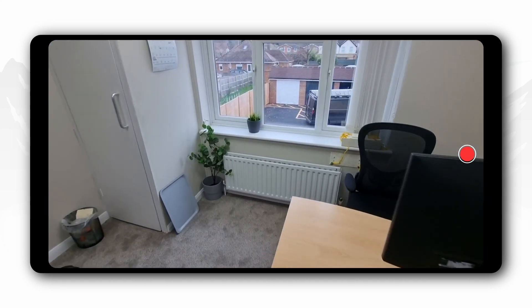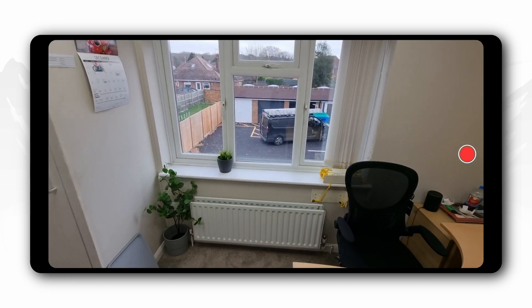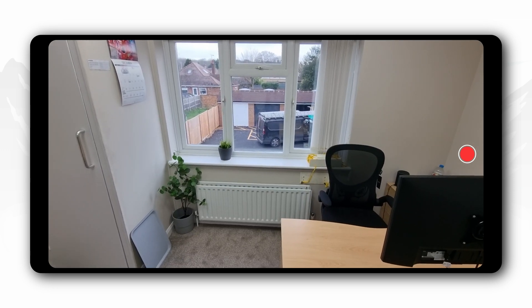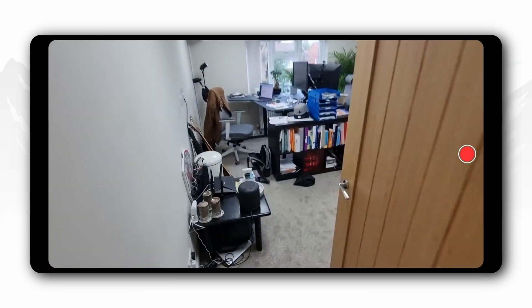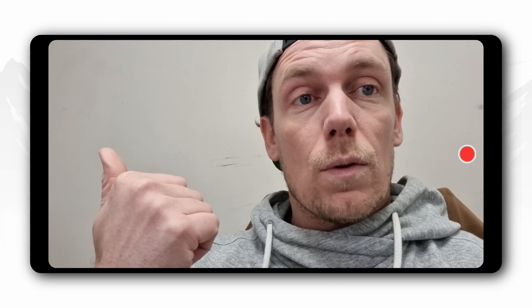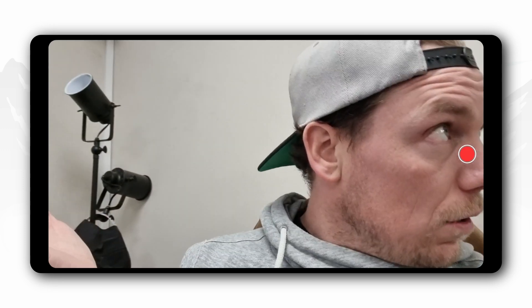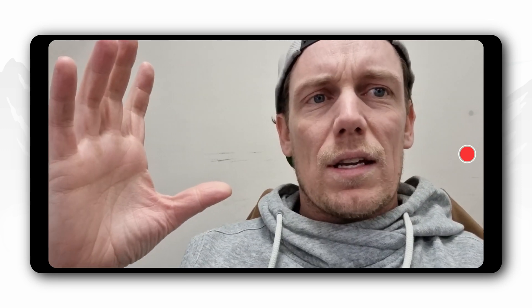And in this room, this room does have a double panel, double convector. However, it's been shortened — not as wide as the window and very short. It's only about 400 or 450mm high, which is abnormal. So an abnormally small radiator in there. My office also has an abnormally small radiator — single panel, single convector. So we've got 200mm of loft insulation, which is very normal. We've got cavity wall unfilled with insulation — a very normal house, and as leaky as a 1960s building. We've got a loft hatch up there which probably lets some air through, and very, very small radiators.